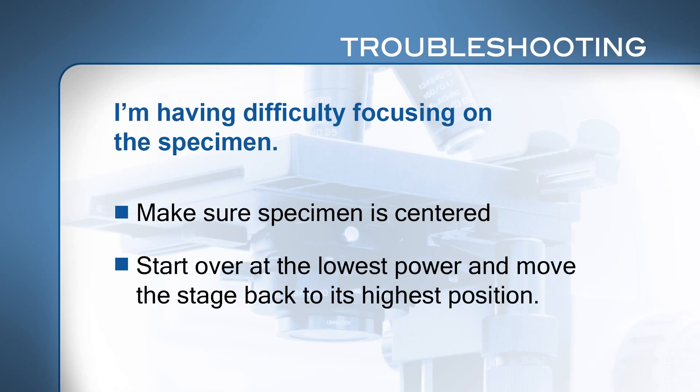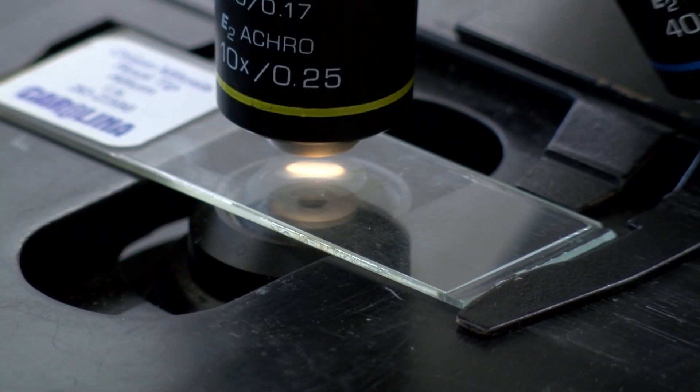Start over at the lowest power and move the stage back to its highest position. If you get frustrated trying to focus, you can easily get so far out of focus that it's easier to start over. You should only need to do minor adjustments at each magnification. When focusing, move the slide just a little bit back and forth with the slide holder knobs — your eyes can see motion better than stationary objects.